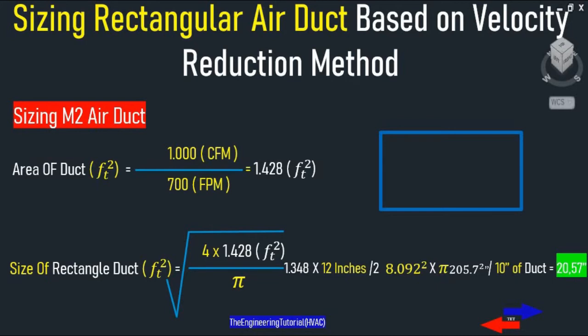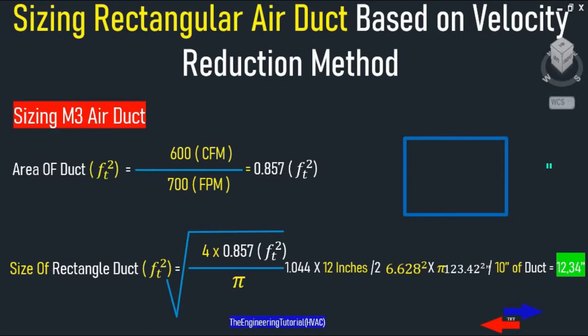So if you divide 205.7 square inches over 10 inches height you get 20.57 by 10 inches. For M3: 600 CFM divided by 700 FPM, square root of 4 times 0.857 divided by pi, times 12 inches divided by 2 squared times pi — that gives us 123.4 square inches. So 123.4 square inches divided over 10 inches height gives 12.34 by 10 inches.